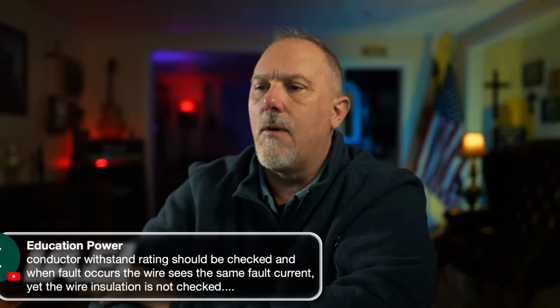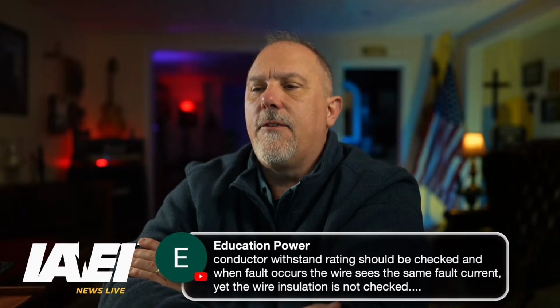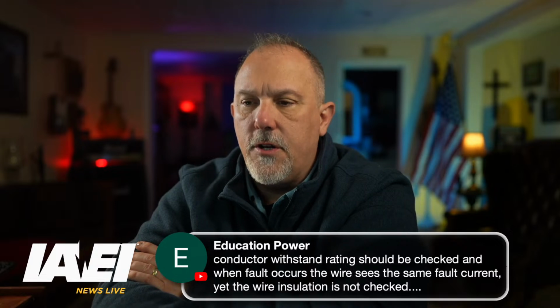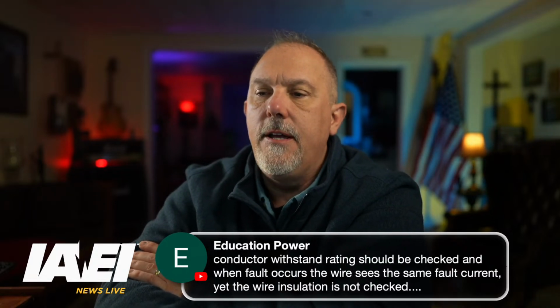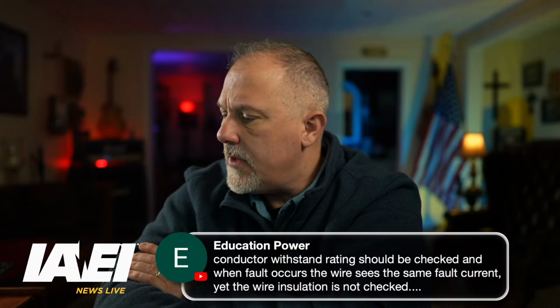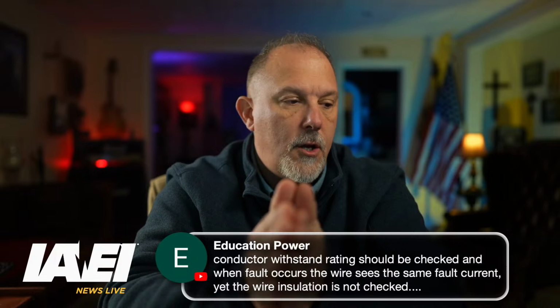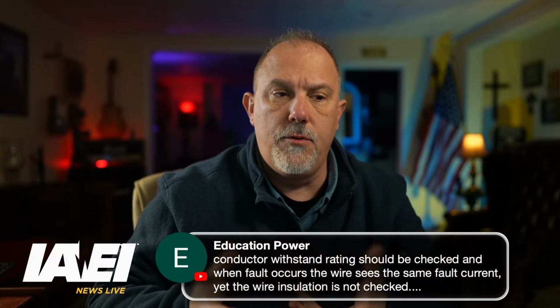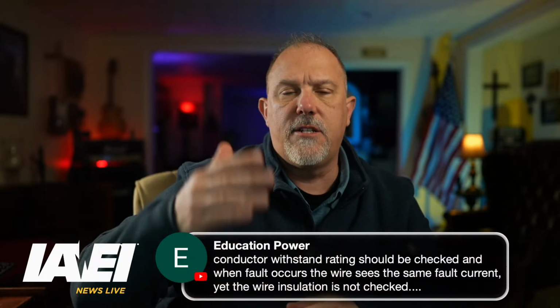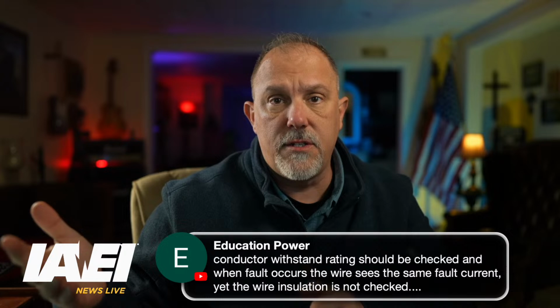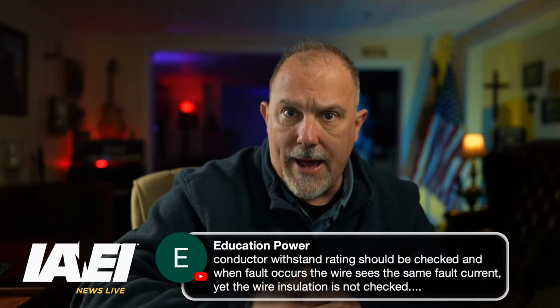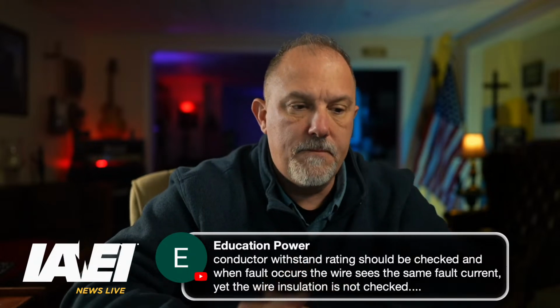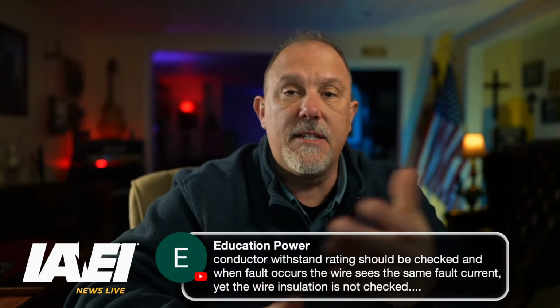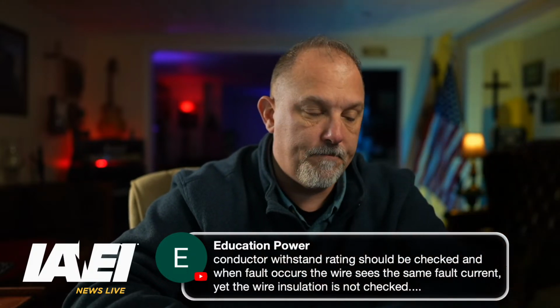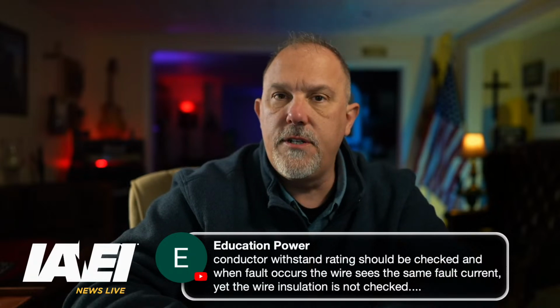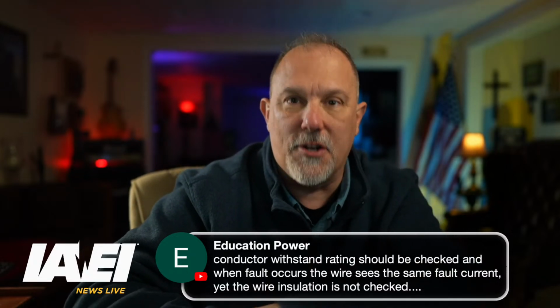Everybody write those down. Robert from Omaha: conductor withstand rating should be checked, and when a fault occurs, the wire sees the same fault current, yet the wire insulation is not checked. So, here's the thing, Robert. When you look at the National Electrical Code, it gives you guidance based upon a conductor, and it just tells you what size overcurrent device is needed to protect that wire. It doesn't specify instantaneous pickups or short time delays. It uses, and we don't typically plot the curves for every one of those.